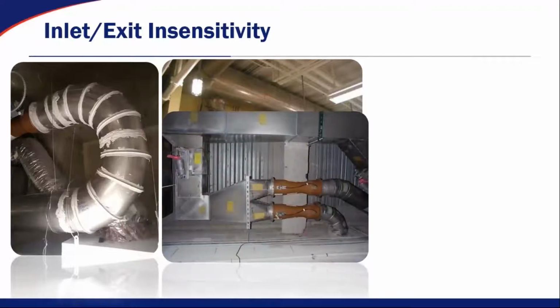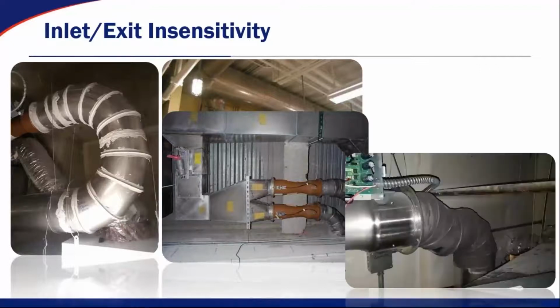This is about the worst case scenario you can get, where you have your main duct riser with a 90-degree bend into another 90-degree bend with a splitter going into 2 Phoenix valves, one with a 90-degree bend going through a hard ceiling and the other one with 2 45s going through a hard ceiling. Again, there's not enough straight duct between the valve and the riser to be able to get a good flow measurement.